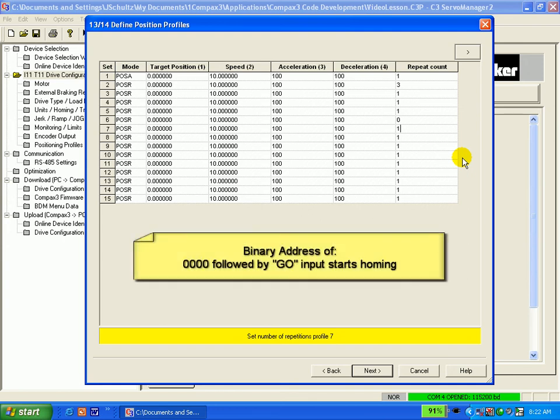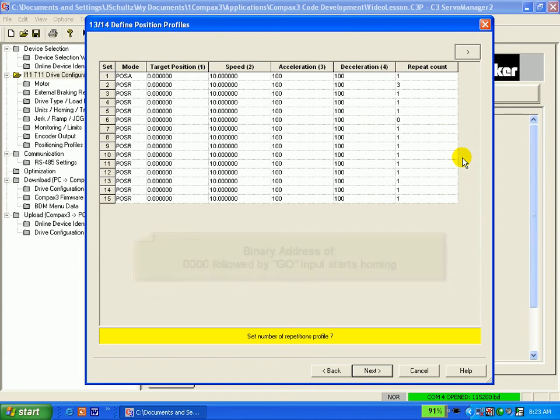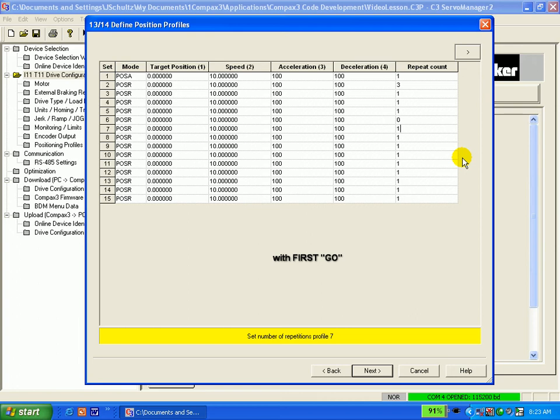In either position mode, if homing is used, a binary address of 0, 0, 0, 0 to inputs 3, 4, 5, and 6 followed by a GO from the PLC initiates the homing sequence. The homing sequence always takes place with the very first GO input following a power cycle no matter what the state of inputs 3 through 6 are, as I mentioned, following a power cycle.